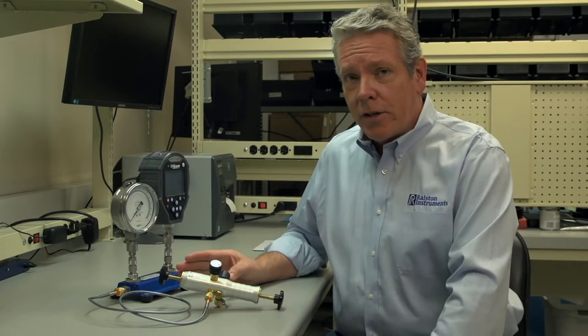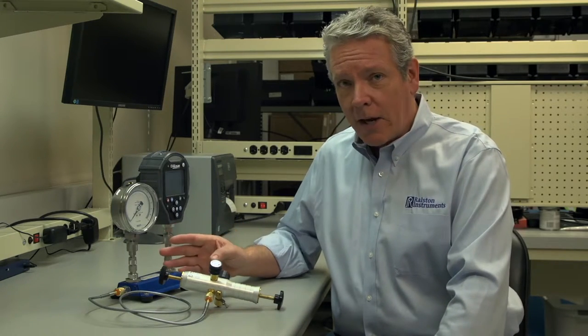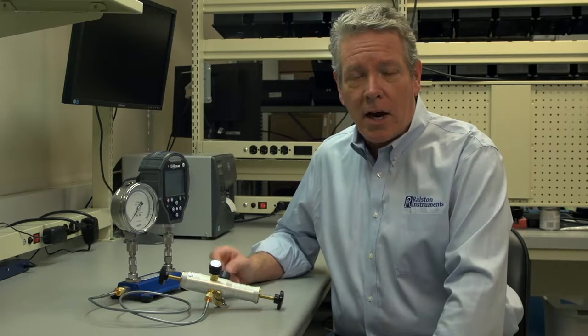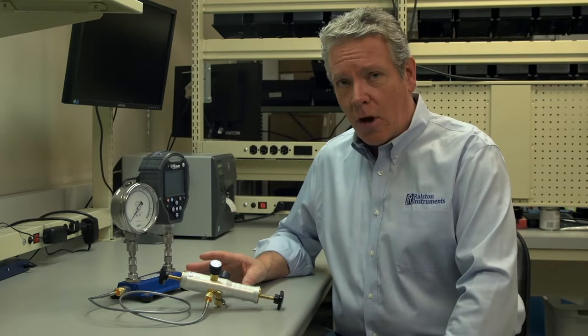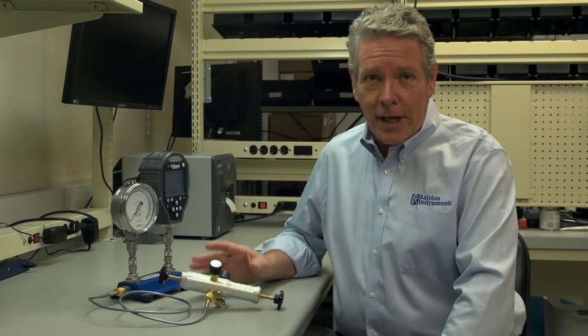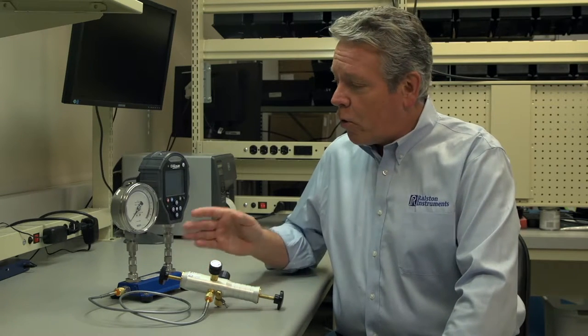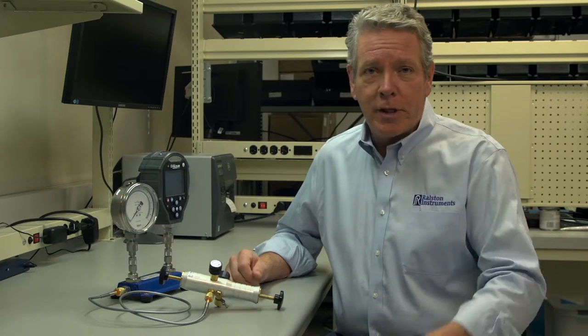I'll demonstrate a calibration test of this quarter percent full-scale accuracy 30 psi analog gauge. Previously we've used the Field Lab desktop software to create and load the calibration test mode with the appropriate number of test points and permissible error.